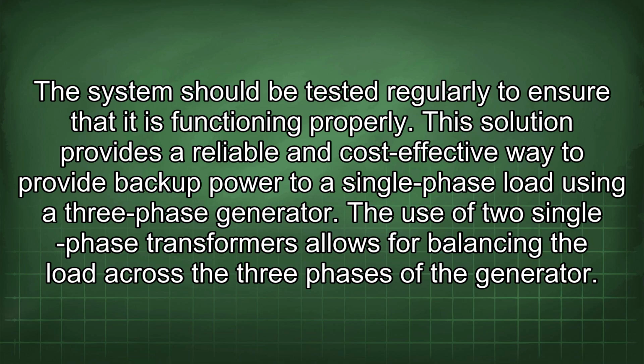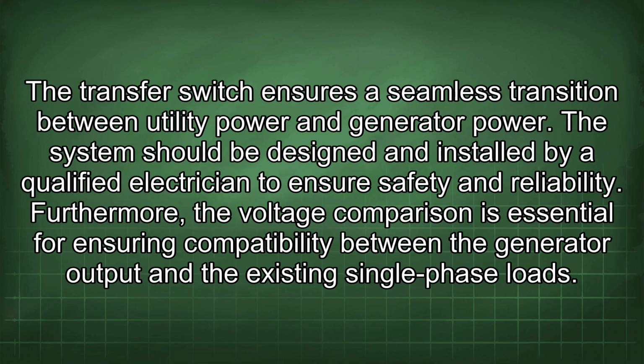The use of two single-phase transformers allows for balancing the load across the three phases of the generator. The transfer switch ensures a seamless transition between utility power and generator power. The system should be designed and installed by a qualified electrician to ensure safety and reliability.